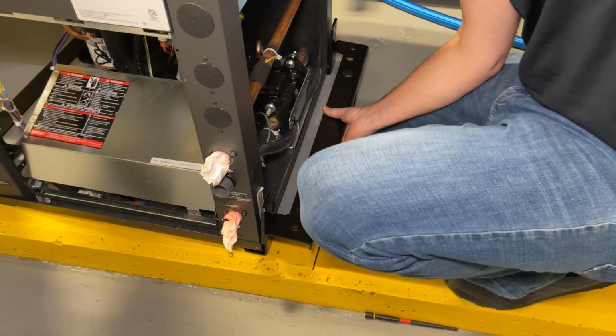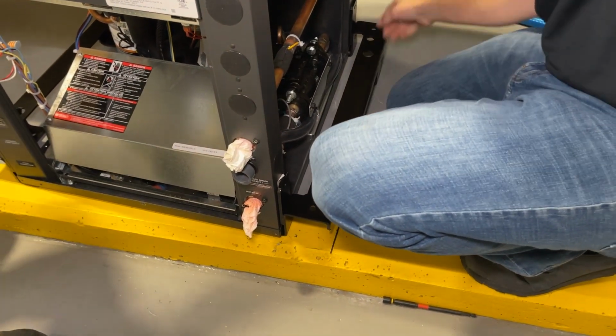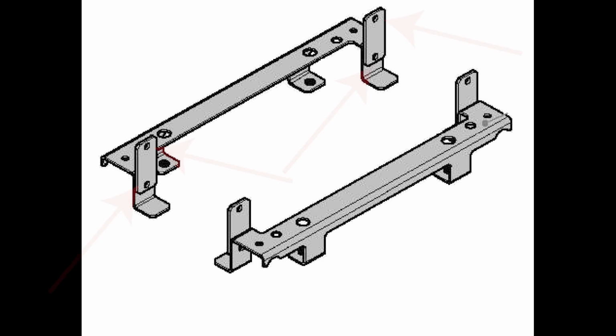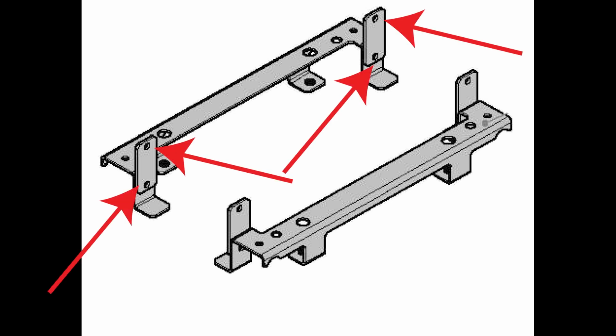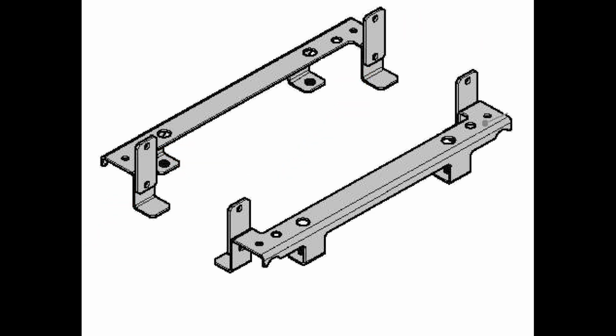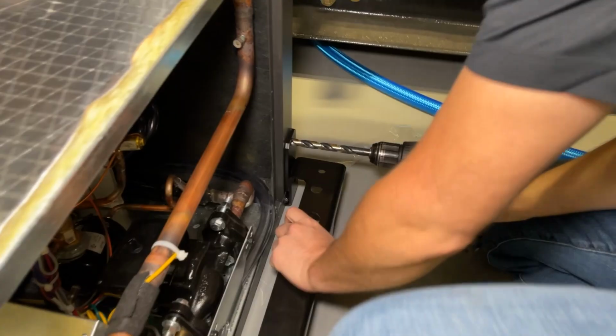Slide the bracket under the side of the unit. Do not tip the heat pump beyond 45 degrees. Excessive tipping can cause the unit to fall over or allow compressor oil to flow into refrigerant lines. Each bracket requires 4 mounting holes. Use caution when drilling through the frame. Ensure no hoses or components are in the path of drilling before starting. Hotstart recommends using a backing plate while drilling to prevent damage to internal components.